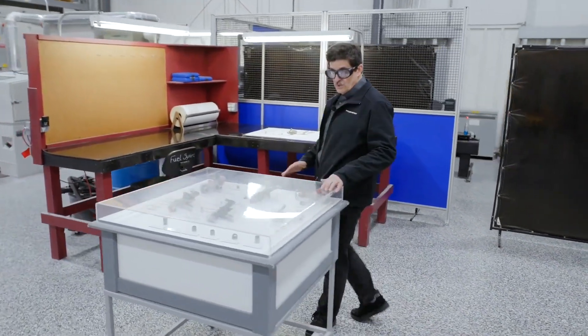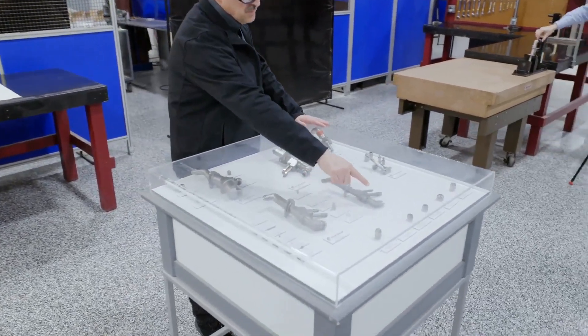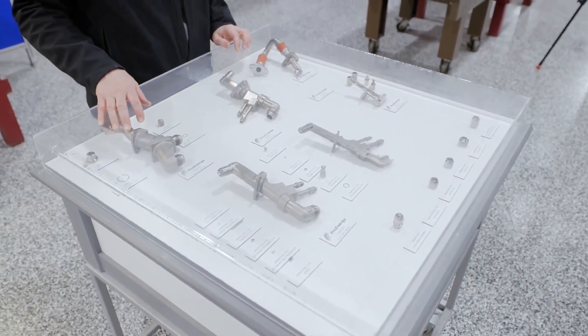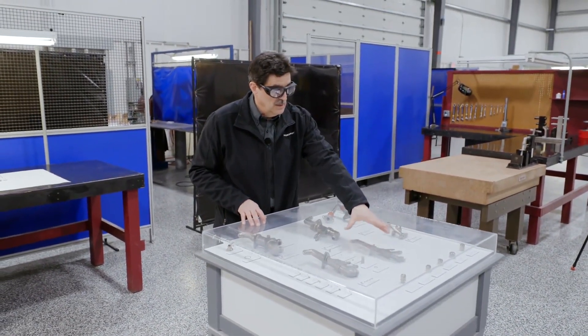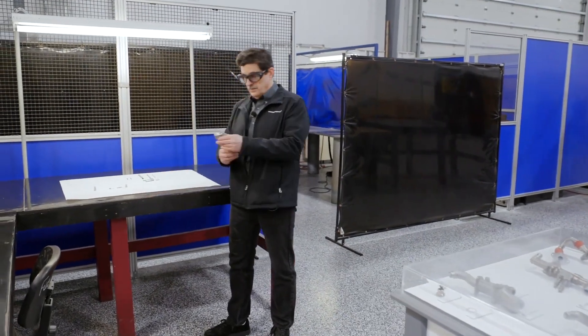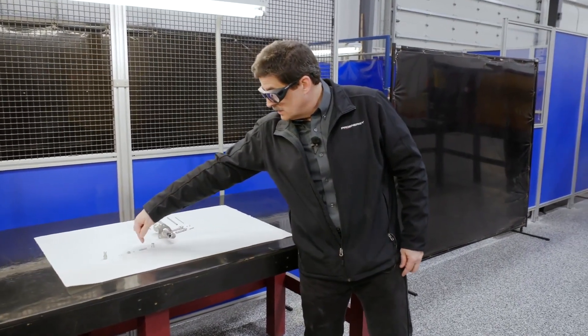There's a cutaway of the dual fuel nozzle — you can see the complexity of the parts inside and the number of small parts that have to be made. Here's your water spray injection nozzle and some other nozzles we overhaul. The ones we new-make are the LM6000 sprint or whisper nozzles and the dual fuel nozzle. You can see the dual fuel nozzle over here with the small parts — the main body of the nozzle and a number of different spray bars and nozzle tip parts that we put together.